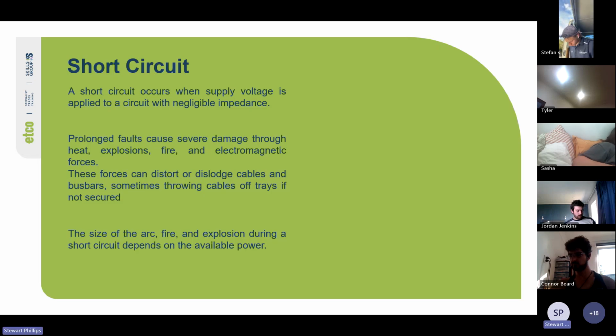Cool. So short circuit occurs when supply voltage is applied to a circuit with negligible impedance. And we talked about impedance. So impedance is the AC version of resistance because there's more than just pure resistance that we need to worry about, which you guys will learn about in second and third year when we start to calculate that. So prolonged faults cause severe damage through heat, explosions, fire, and electromagnetic forces. These forces can distort or dislodge cables and busbars, sometimes throwing cables off trays if not secured. The size of the arc, fire, and explosion during a short circuit depends on the available power.